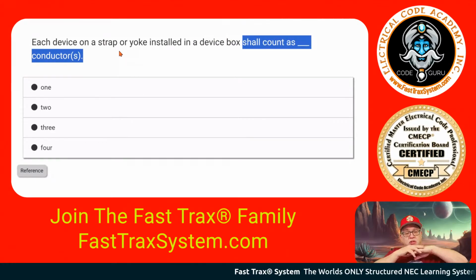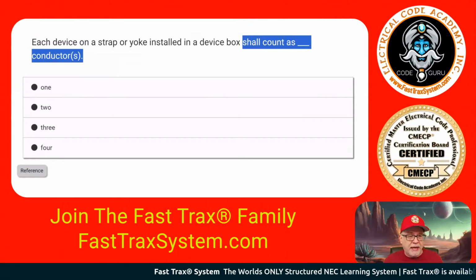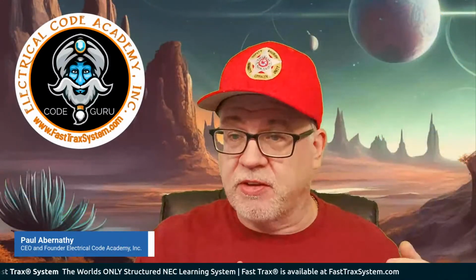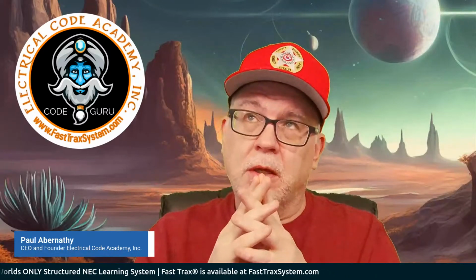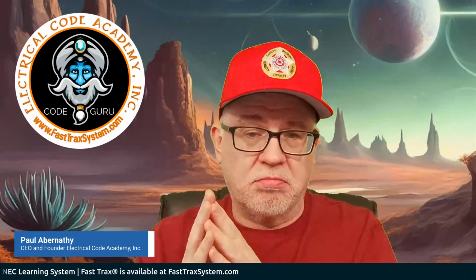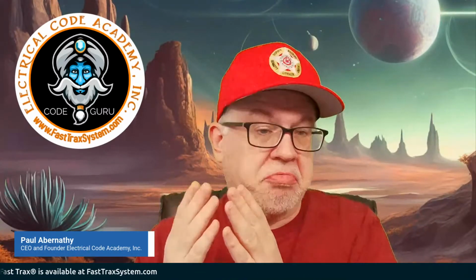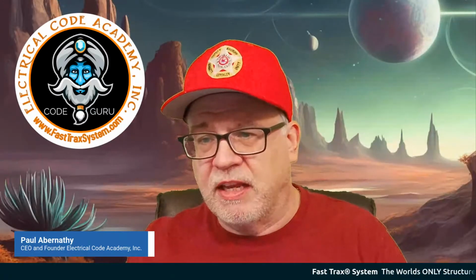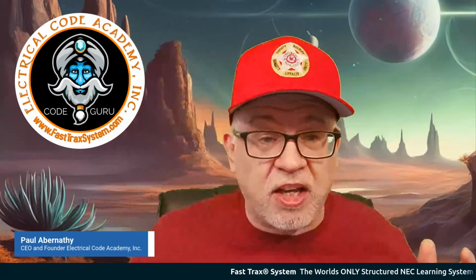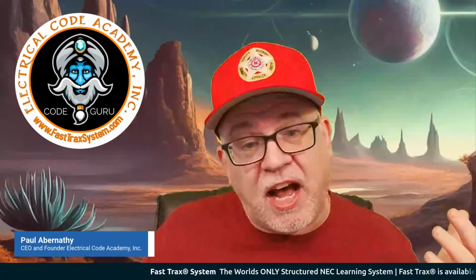So this question should stick out to you right away as a box fill question, because if it's a receptacle, duplex, simplex, or switch, it's going in a device box. Obviously, it's taking up a volume, and the code says it counts as one volume or two volumes, a double volume.